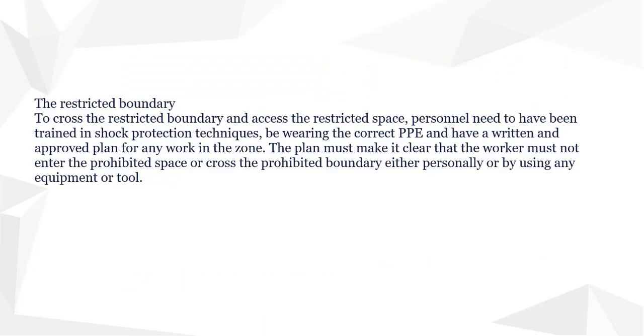To cross the restricted boundary and access the restricted space, personnel need to have been trained in shock protection techniques, be wearing the correct PPE, and have a written and approved plan for any work in the zone.